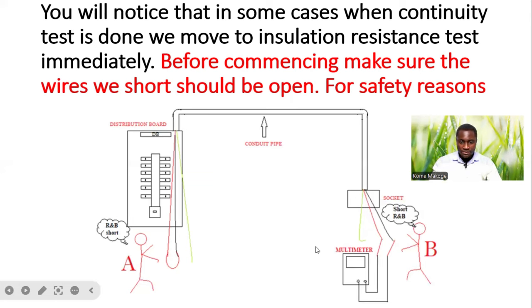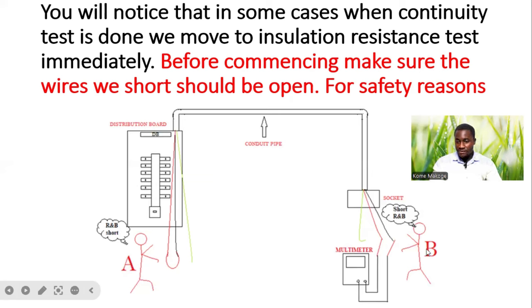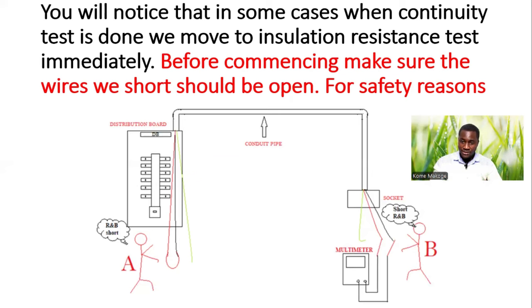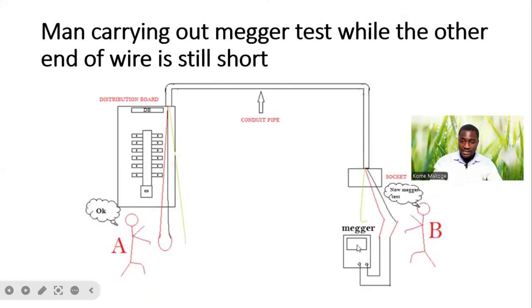Looking at the graphic, we have one person at the DB side and another person standing at the field side or at the socket outlet. The first person has done with the continuity test. He now moves to performing the megger test or insulation resistance test. However, the man at the field side is still carrying out a megger test while the other end of the wire is still shorted.